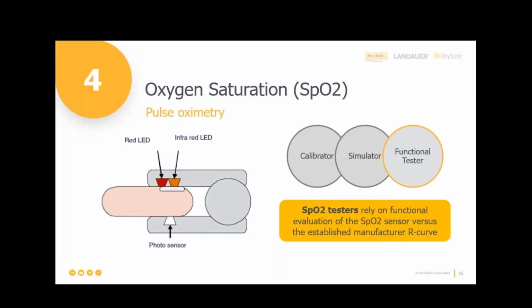And it's important to remember that when we're thinking about, is this vital sign parameter measuring well? What are the things that could go wrong with the sensor? And we've already commented that it is the sensors and the connections on the patient that are going to fail first and most often. So we need to know when it's time to just go replace the sensor first and see if that solves the problem. Take the bad sensor or the bad extension cable, cut them, take them with you away from the clinical unit.